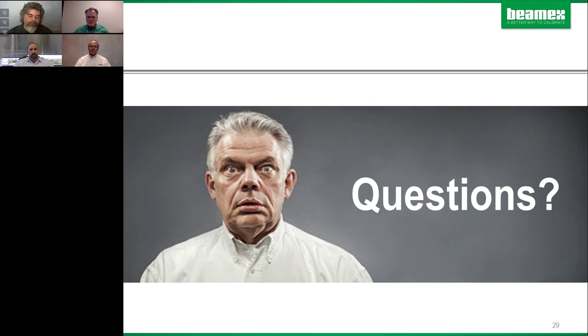How do you identify drifting instruments? Well, maybe I'll take a stab at it. Roy, you can chime in. I would say technicians have a gut feel. They know stuff is drifting. They know that stuff is pretty reliable. But my opinion is that of your critical instruments, you need to document those and see what the actual drift is in your process, in your plant, under your conditions. Because depending on what part of the country you're in, the same instrument might drift a different way. If you're way up north, harsh cold could affect it one way versus down in Florida where you have really nice weather, or California.